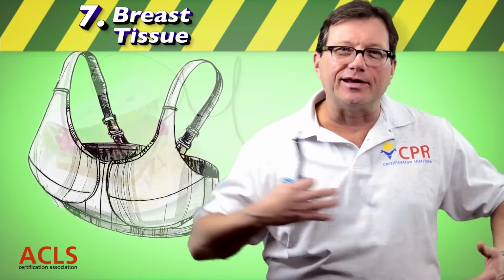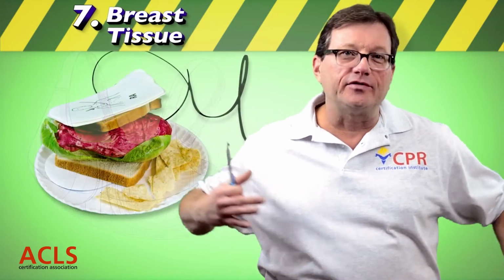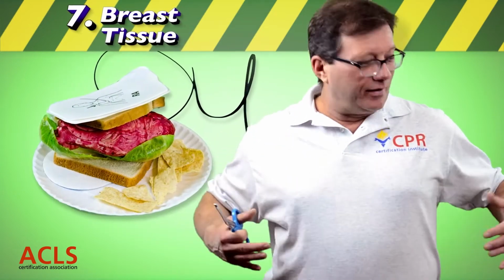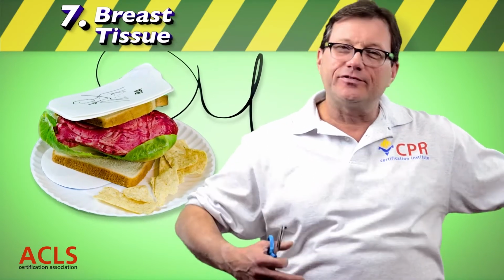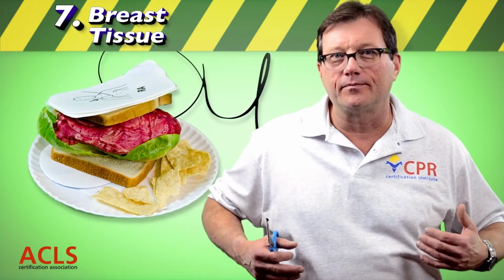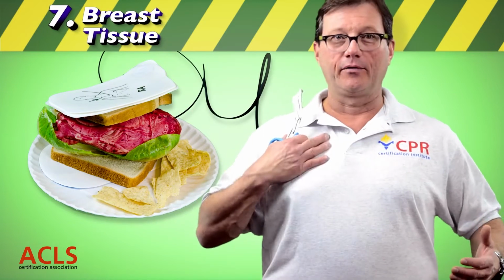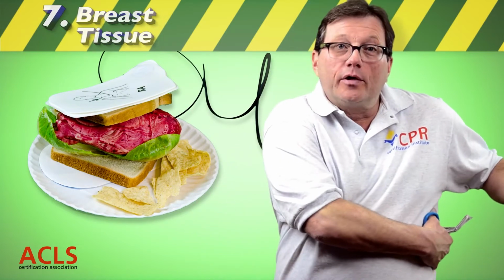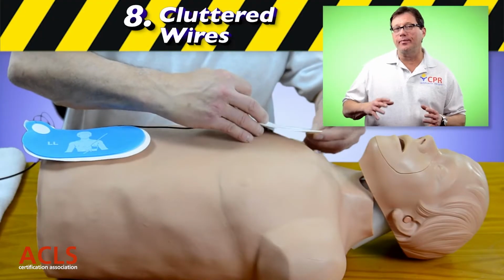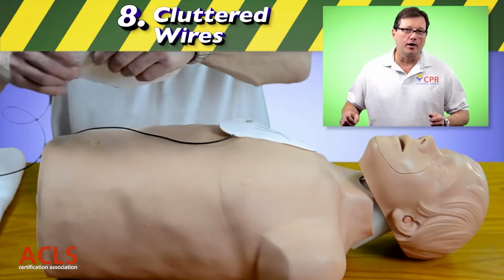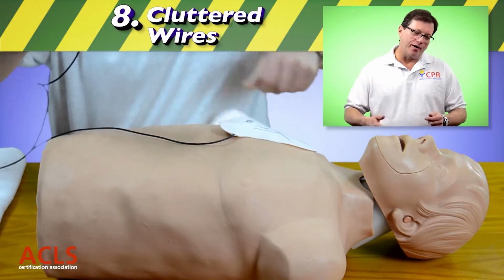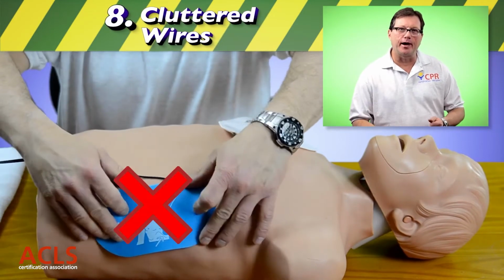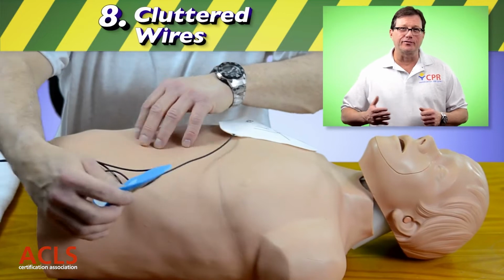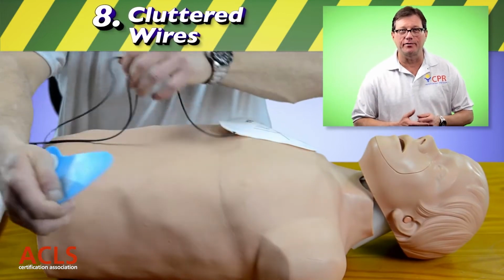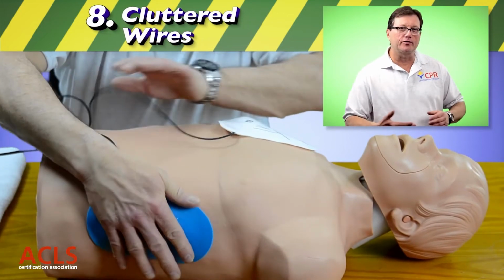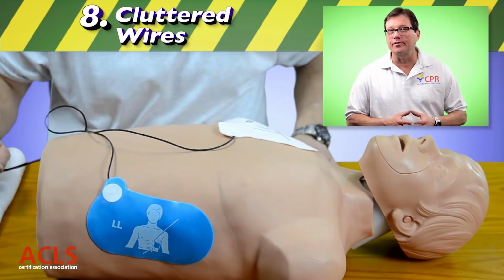Not only do we have to have the heart in between the pads, but we have to have the pads as close to the heart as possible. If I were to put a pad on top of breast tissue, that's just further the energy has to go to get to the heart. So again, on large-breasted women, high right, lift the breast out of the way, go underneath the breast. Now remember, when putting the pads on the patient, there's wires coming off of those pads. Make certain that the wire doesn't accidentally get caught underneath the pad. Again, anything that diverts energy away from going through that heart is a bad thing. So again, make sure that the wires don't get stuck underneath the pads when you're applying them to the patient.